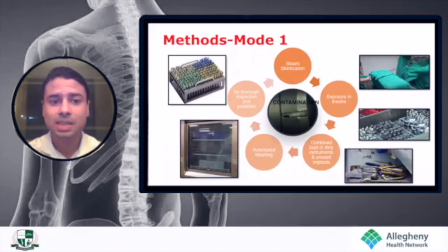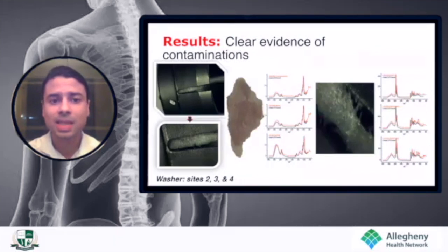We randomly selected 6 pedicle screws from sterilely wrapped implant sets and performed a detailed analysis using a variety of laboratory techniques such as optical microscopy, scanning electron microscopy, EDS, and FTIR. The results showed that these implants had contaminants such as corrosion, polysaccharides of unknown origin, and soap residues mixed with fatty molecules.